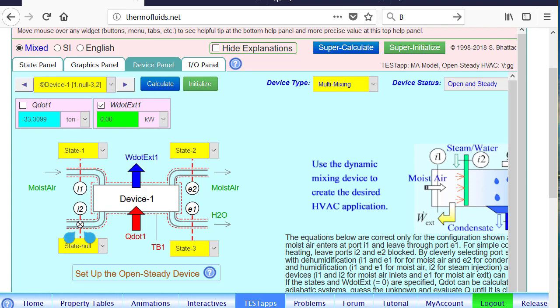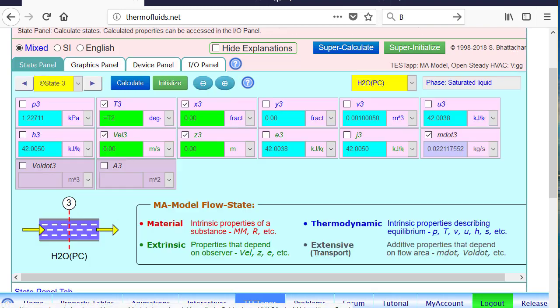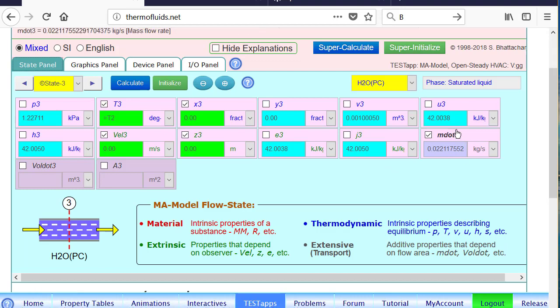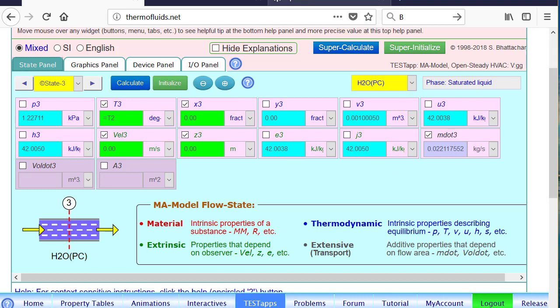So 33.3 ton is the refrigeration capacity needed for this particular cooling. And of course, you can go back and take a look at state three. As you can see, the amount of water condensate is found here in kg per second. We can convert it to kg per minute if necessary.